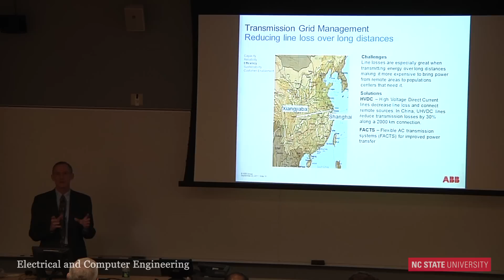For transmission technologies, when you have to go long distances, HVDC technology lowers losses. This is an example of what we've done in China—about 30% fewer losses. This is ultra high voltage, I think 800 kV. You have lower losses and only 2 wires, and you don't have the inductance or AC current effects that you get with AC, so overall you do have lower losses.